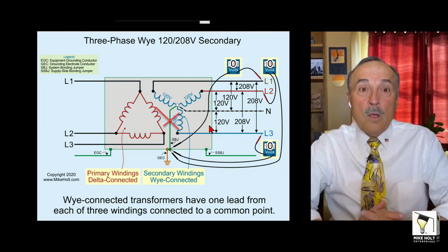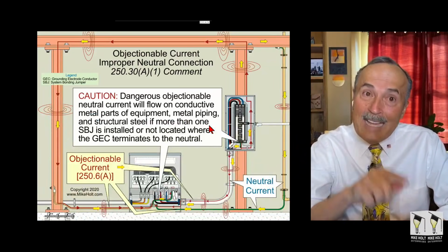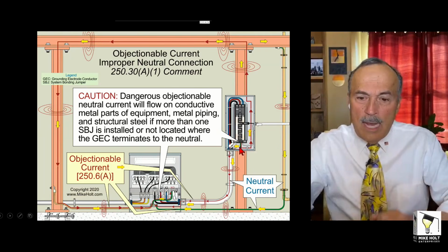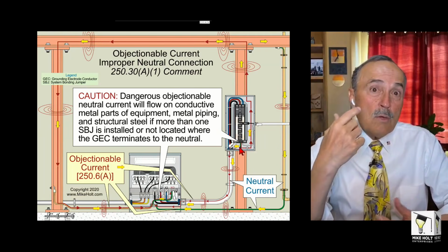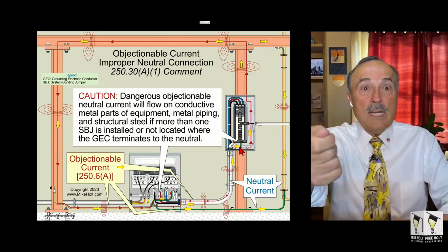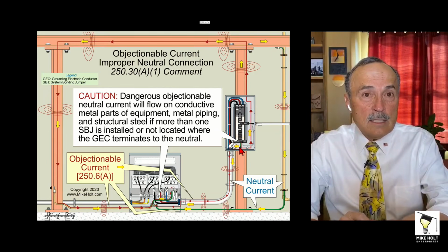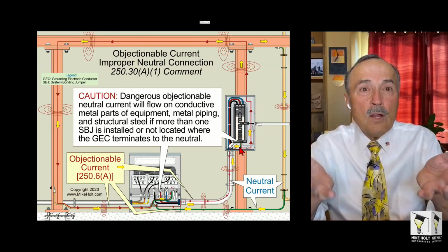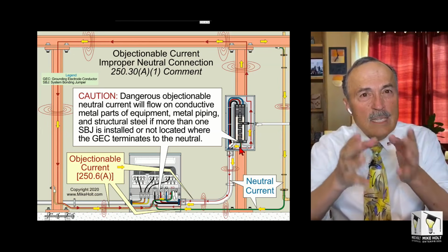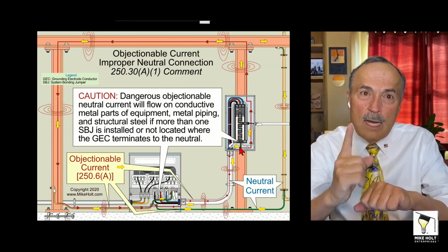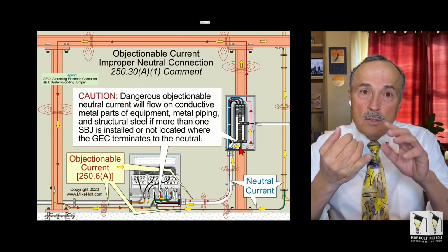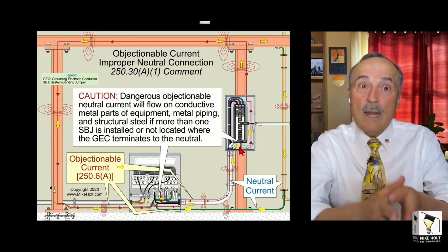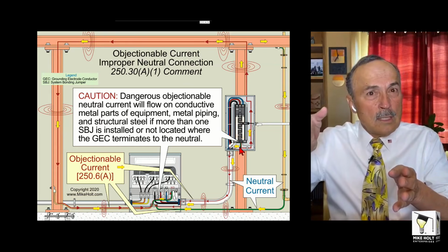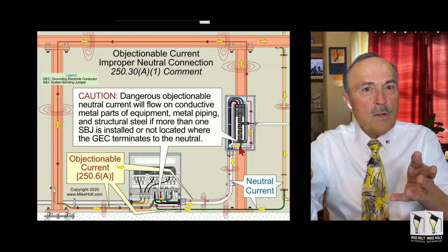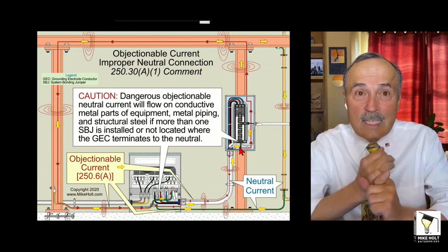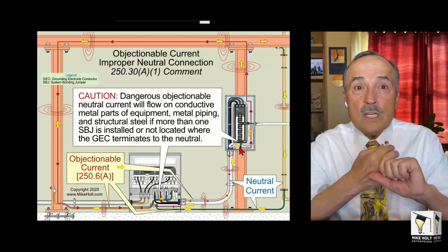But hopefully this is what you're getting. It's a review. What happens if you install the system bonding jumper at the transformer, which is where I've been showing them in general, and then somehow a person sees that strap or that screw and says, okay, there must be a reason they got that in the panel, and they make a connection here at the system, separately derived system? Well, now you're going to have parallel paths for neutral current. Every single system is to be bonded and grounded at one point, which means you take that neutral and bond it to the case, and then you take the case and the neutral and ground it. You don't ever do a neutral to case ground again, because then your neutral and your equipment grounding conductor are in parallel. Violates 250.6 objectionable current, violates 250.142.